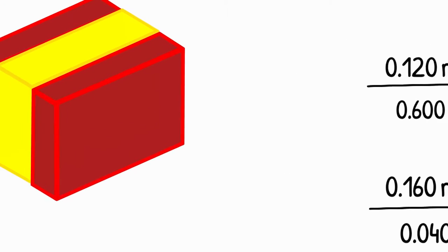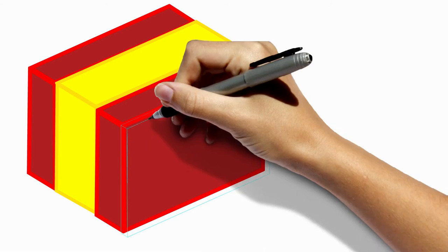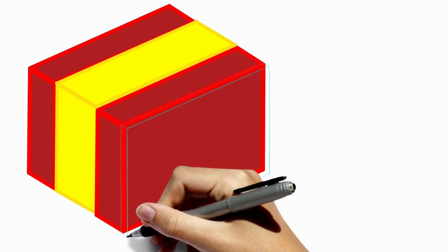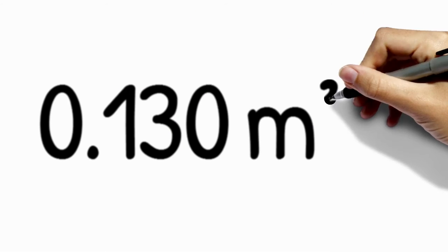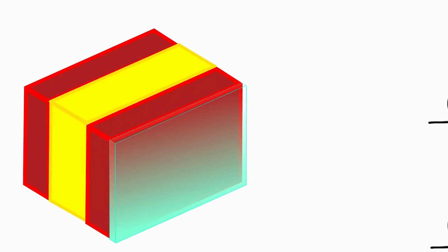We're almost there, but we still have to account for surface resistance, the added resistance of a thin layer of still air directly in front of our building element. On the interior, that adds 0.13 square meter times k over watt to the resistance.